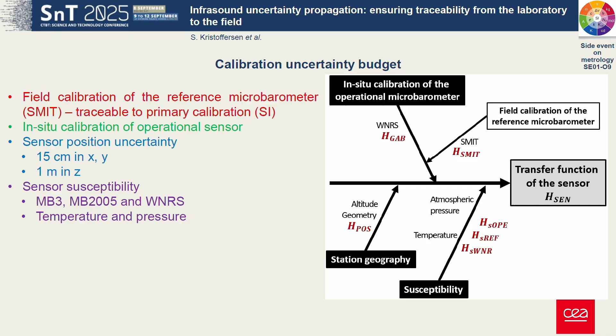So the SMIT, Système de métrologie infrasonnaire de terrain, is an in situ infrasound metrology system. If you look in this picture, the metal cylinder is the SMIT, and it is a sealed cylinder with a loudspeaker that generates an infrasound signal. You can see in that picture a reference microphone that's attached, and we can connect our microbarometer and then do a calibration relative to this reference microphone, which has been calibrated. And the idea there is that we can calibrate this microbarometer in the field in the ambient conditions. And now we have a microbarometer that is traceable to our primary calibration.